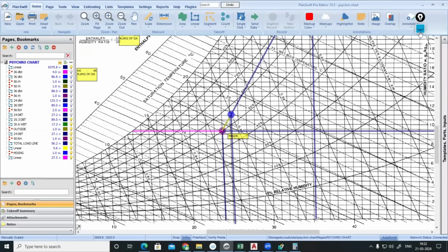But even though, the coil surface temperature, we can't keep at 13 degrees. This is 10, 11, 12, 13. We have discussed that. This is the dew point temperature. But the coil surface temperature, we can't keep at 13 degrees Celsius. Why?